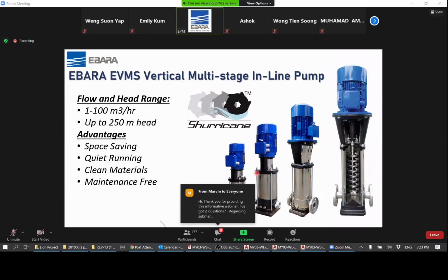Very clean materials. Normally, these pumps are made in either fully stainless steel parts, and maybe just the top and the bottom cast iron. Normally for cold water application, we have stainless steel 304 and just the top and the bottom cast iron, but in many industrial applications, it will be completely fully stainless steel 304, which means that any parts that are in contact with water is 304. So it prevents rust and brown water from the pump.